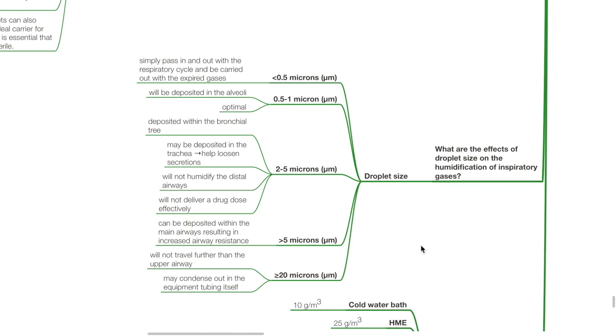Effects of droplet size on humidification: droplets less than 0.5 microns pass in and out of the respiratory cycle and can be carried out with expired gases. Droplets of 0.5–1 microns will be deposited in the alveoli — this is optimal. Droplets of 2–5 microns are deposited within the bronchial tree or trachea and help loosen secretions, but will not humidify distal airways or deliver a drug dose effectively. Droplets of more than 5 microns can be deposited in the main airways, increasing airway resistance. Droplets of more than 20 microns will not travel further than the upper airway and may condense out in the equipment tubing.